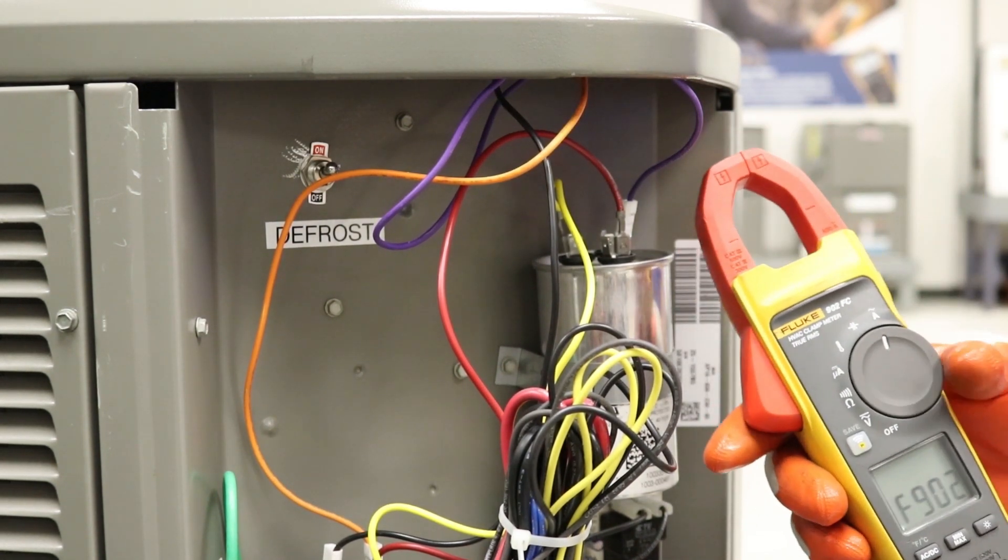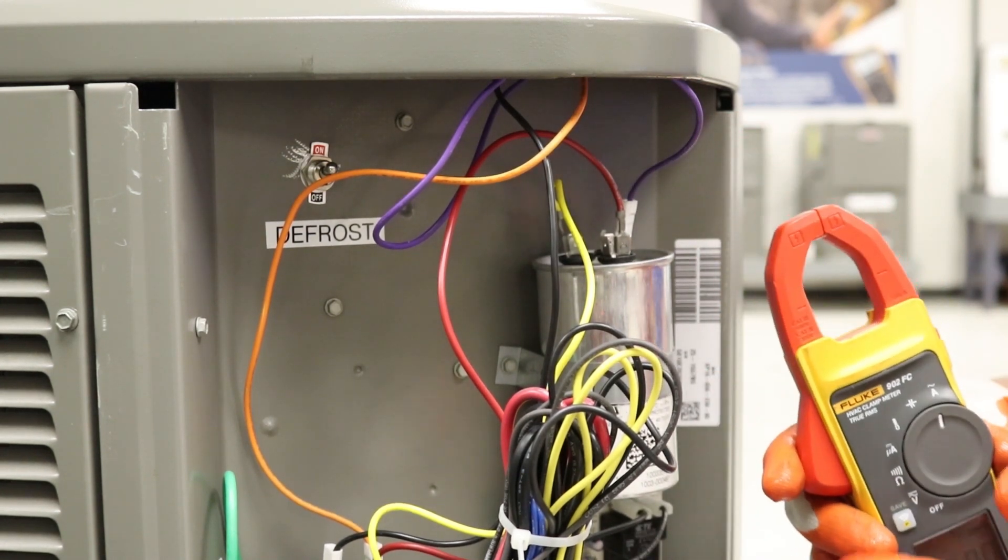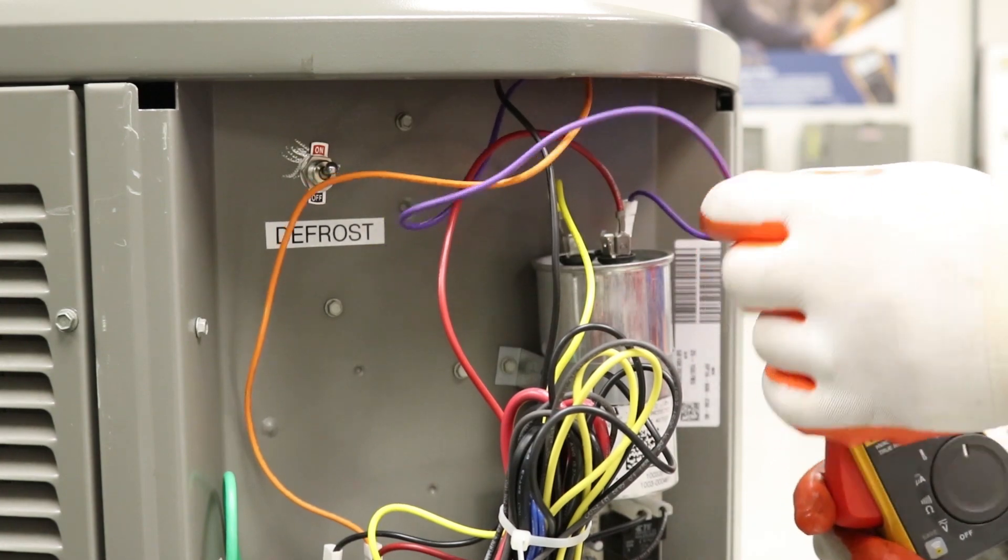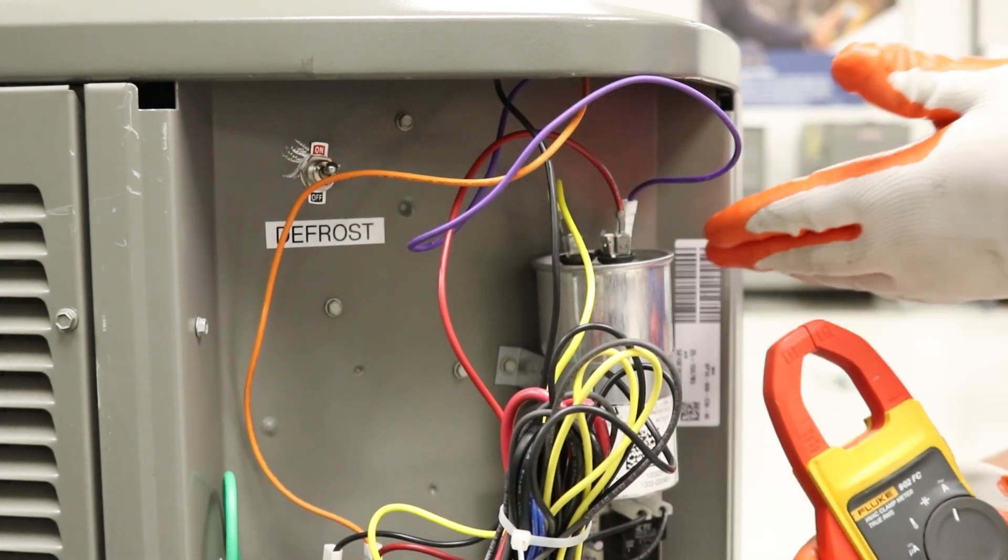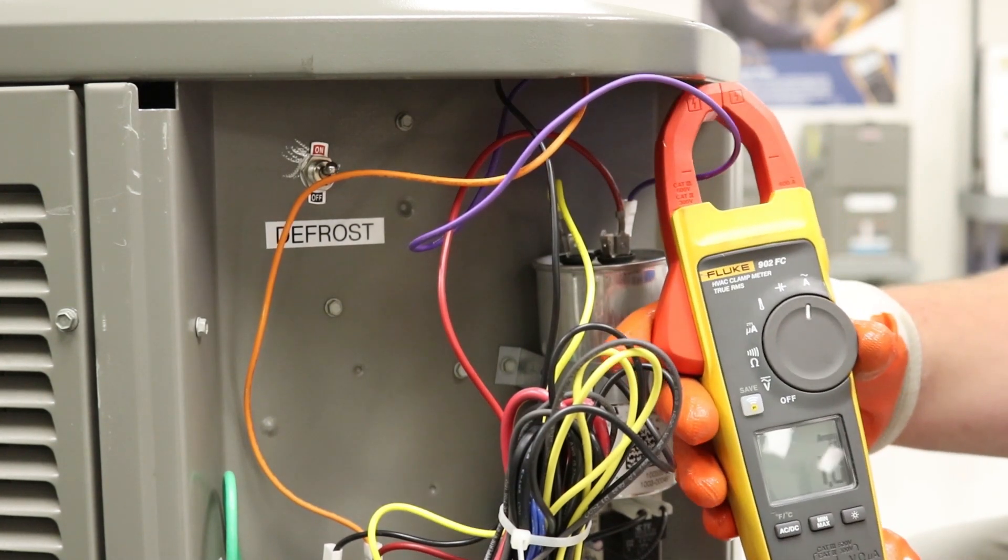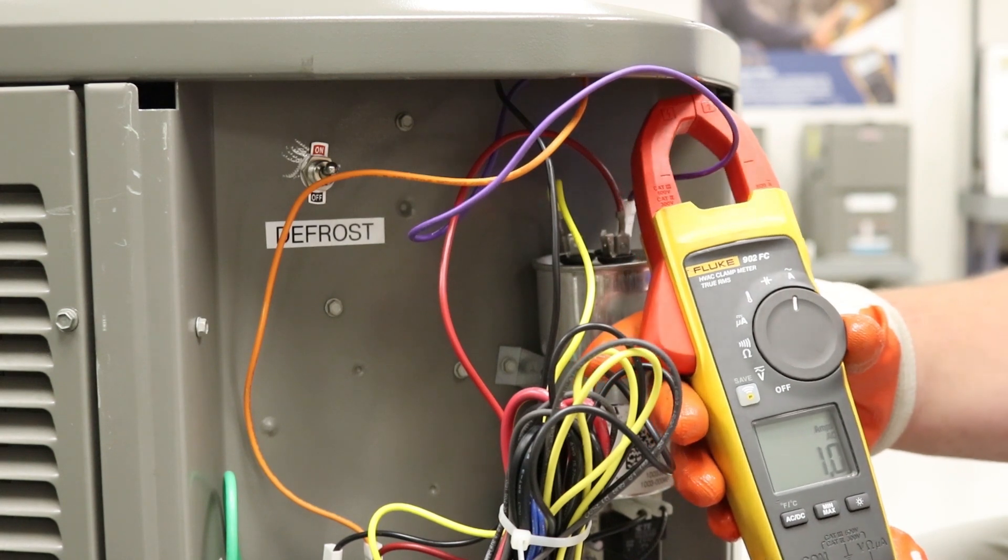Once our meter comes on, first, we're going to check the amperage of the fan terminal, which you can tell it's hooked up and says right on top of the capacitor that that is the fan terminal. So we'll go ahead and hook up our meter. And it says that our amperage on the fan terminal right now is 1.0.